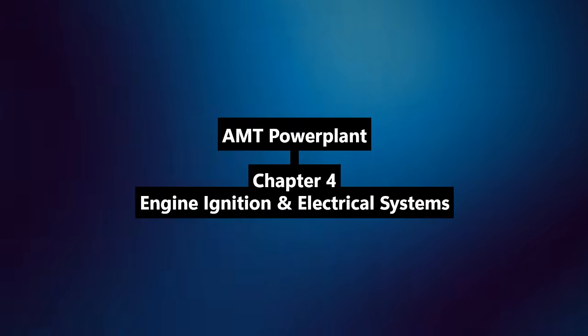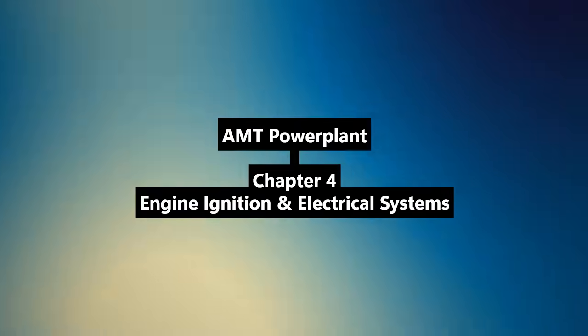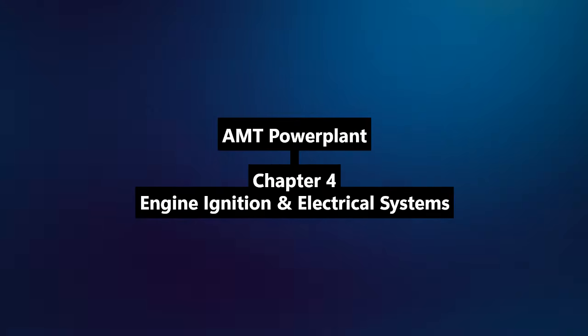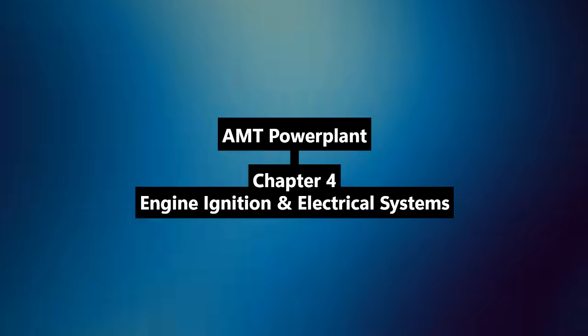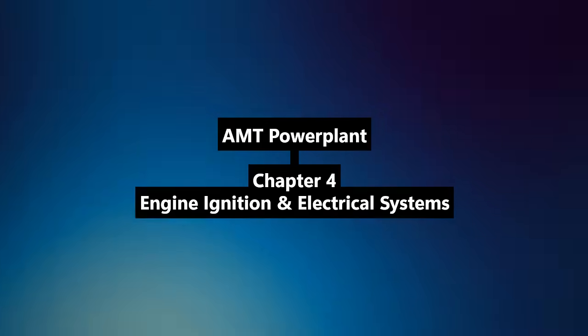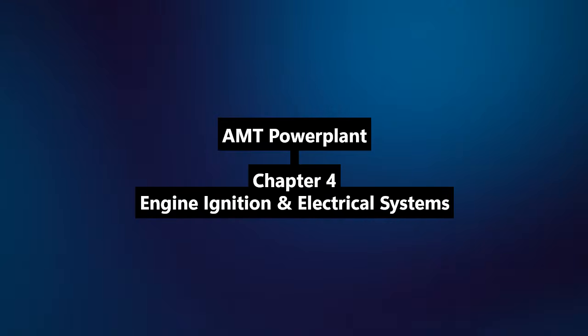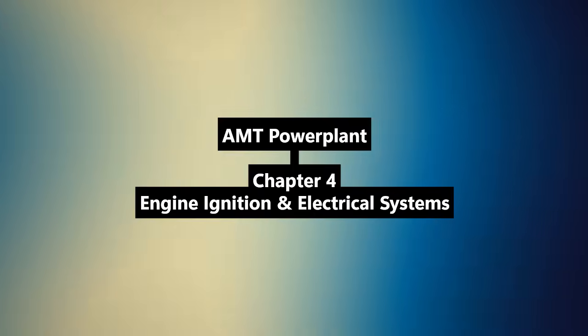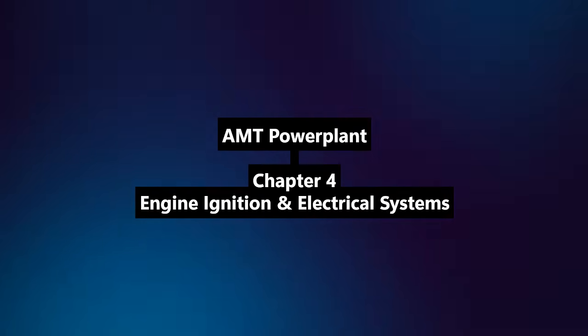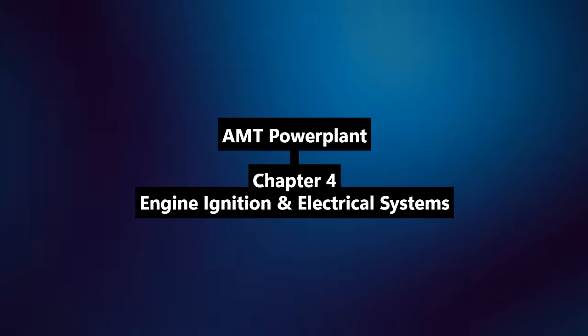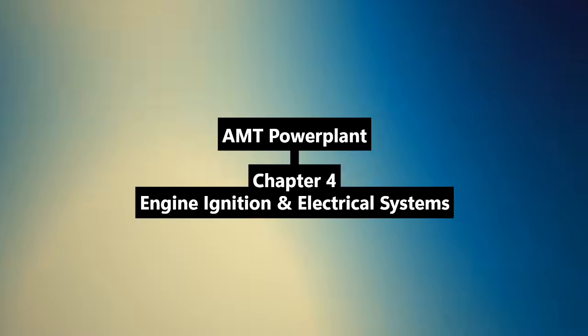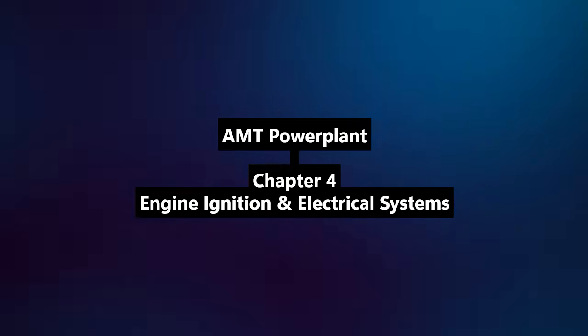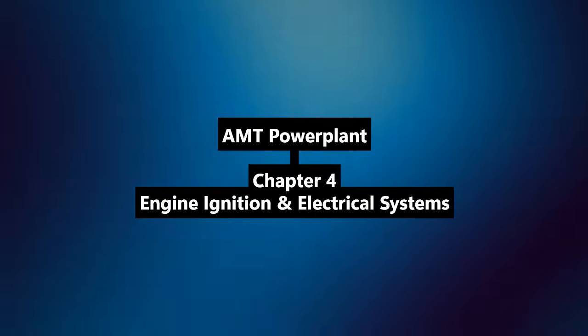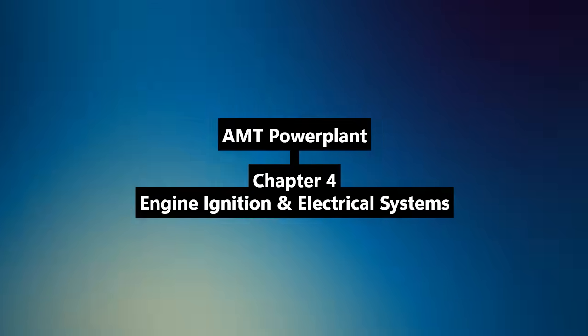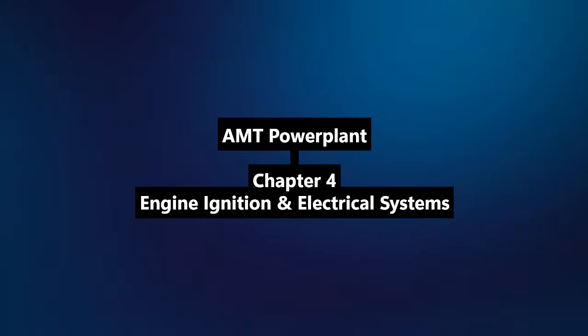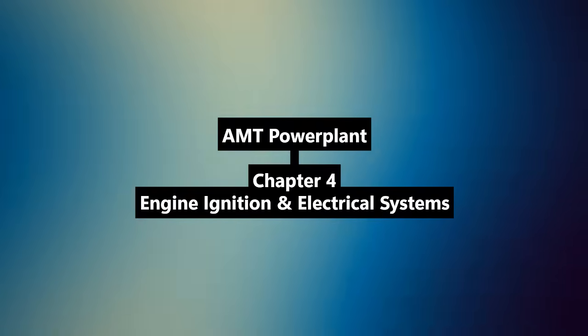What's their purpose? The pigtails. You'll see these flexible, low-resistance connections, usually made of braided copper wire, attached to most high-current-carrying generator brushes. Why are they needed? Their main purpose is to provide a reliable, low-resistance path for the electrical current to flow from the armature, through the brush material itself, and then out to the generator's external terminal or connection point. They carry the bulk of the current, not the spring. So the spring just provides pressure, the pigtail carries the current. Exactly. These pigtails ensure good electrical conductivity and also allow the brush to move freely within its holder as it wears down over time. Their connections need to be secure and checked for corrosion or damage, and they should never restrict the brush's movement. Okay, makes sense.